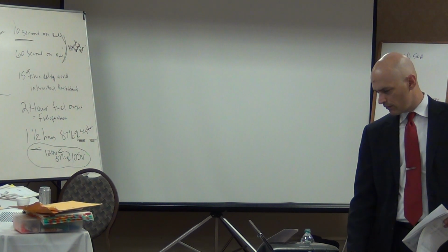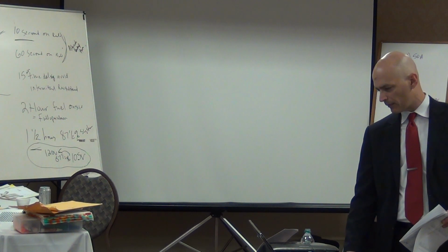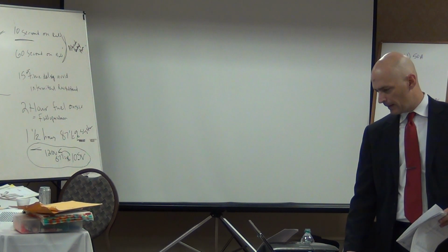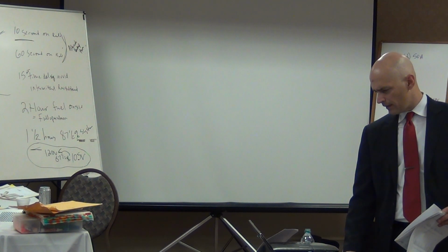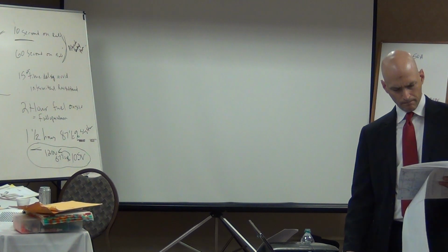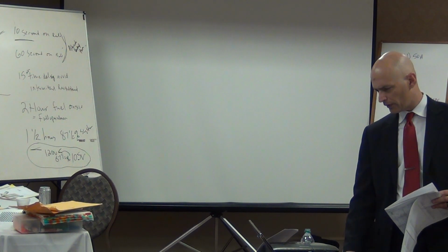We know it's number 8, maybe single phase, 40 amp breaker. Yeah, the feed of it is a single phase, 2 pole, 40 amp. Look on the panel schedule. Dig it up, I don't know why I've got a list of... class. And the breaker type for that panel is MLO, so there is no main there at the panel, it's just a sub thing.